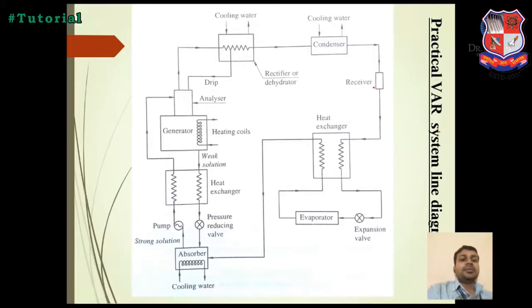The NH3 liquid is evaporated in the evaporator and absorbs heat from the closed space or unclosed spaces and produces a cooling effect. Then after the evaporator, the NH3 vapor passes through the heat exchanger to the absorber. The NH3 vapor passes through the heat exchanger, and we see that there is a large temperature drop compared to the entry of the expansion valve. There is a positive temperature before entering the expansion valve, and after the evaporator there is a negative temperature.